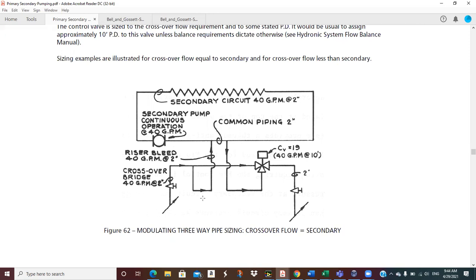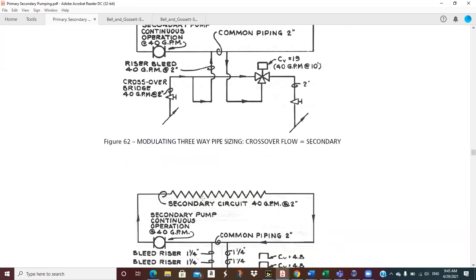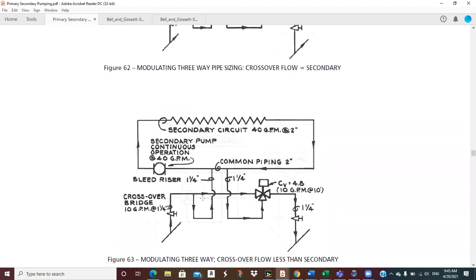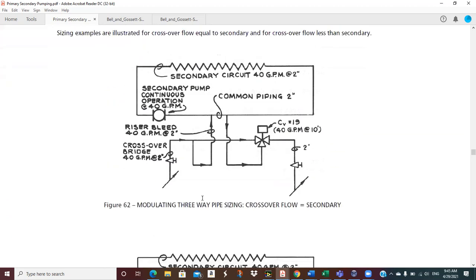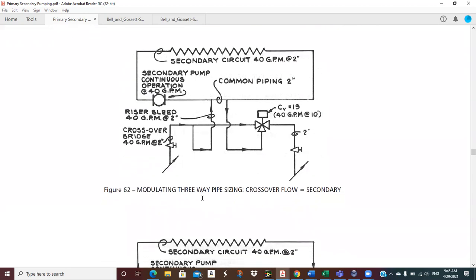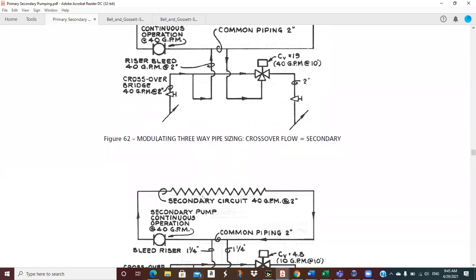I've got that number memorized. And then you divide that into 40 because the valve equation is what? GPM Q is equal to CV times the square root of delta P over specific gravity. And it comes out 19. I checked it this morning. So, you know, you guys are more than able to size the CV for that. If you come down here, and of course, we see the pipe size here. We got 2-inch pipe every place.